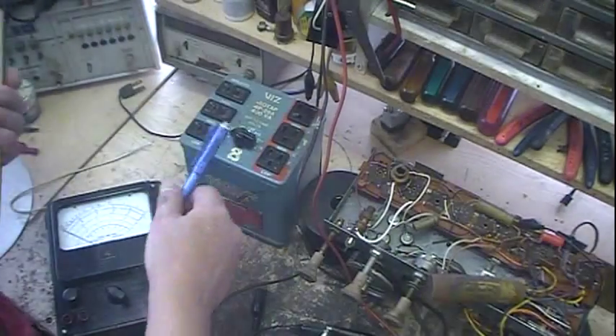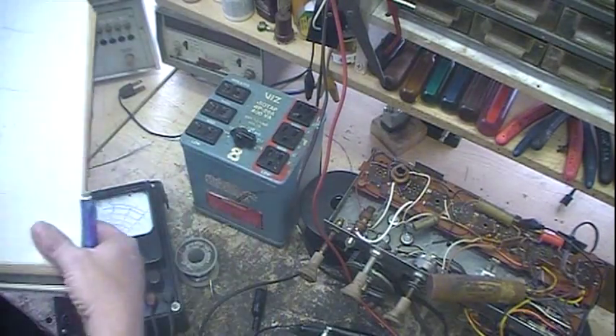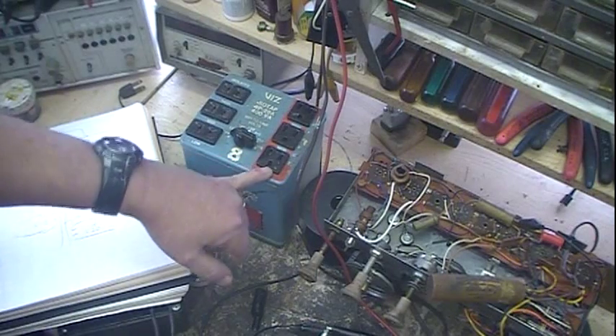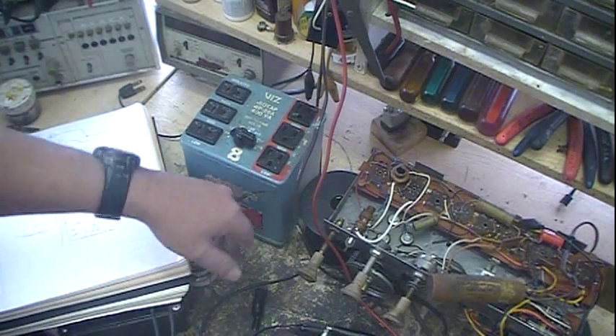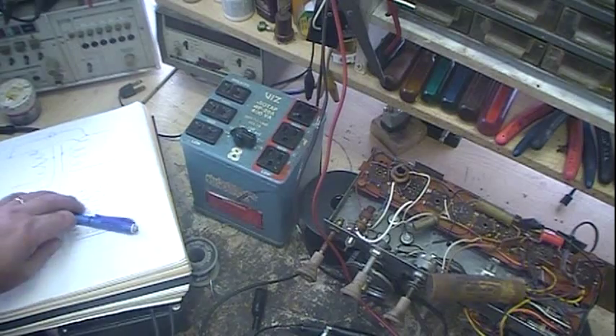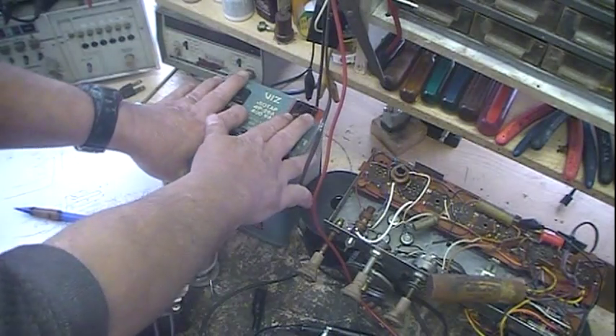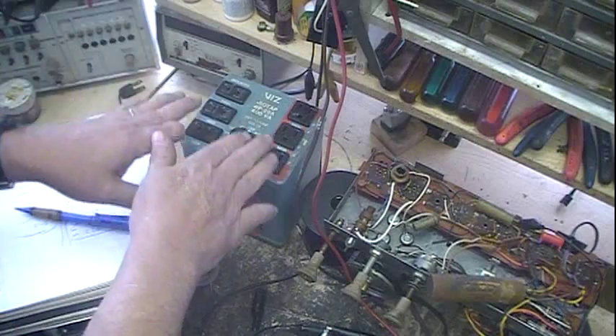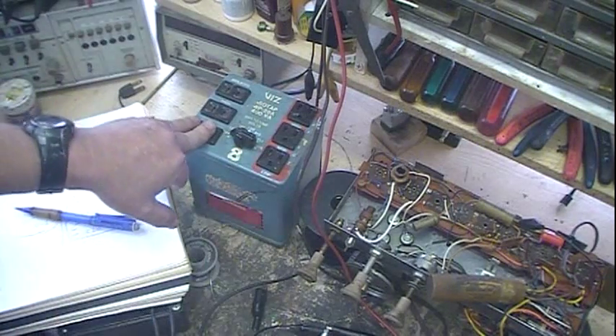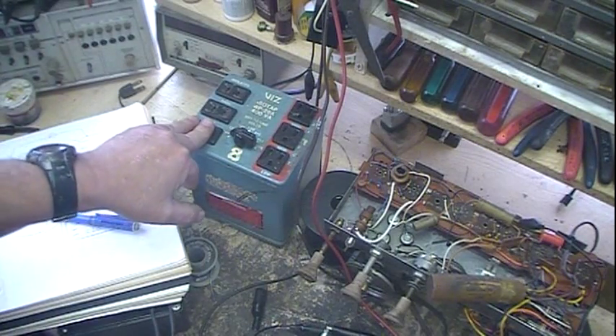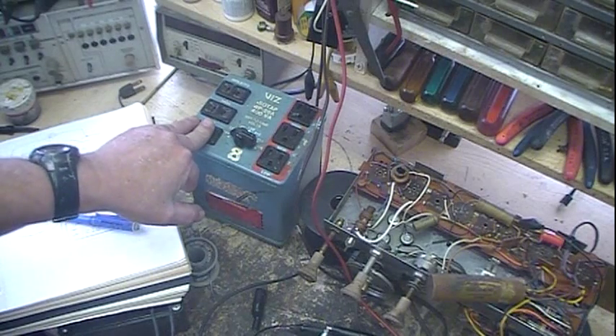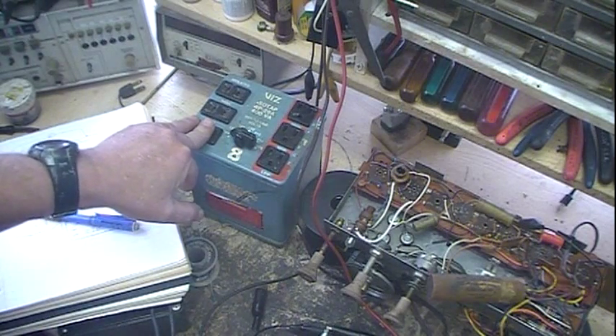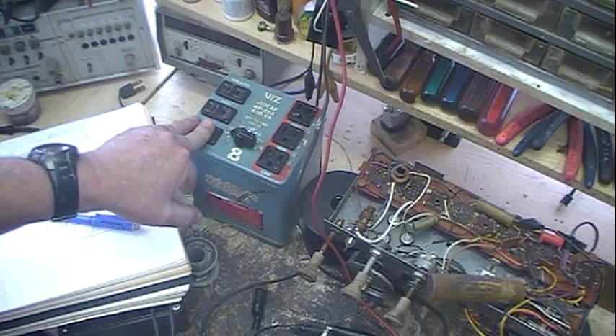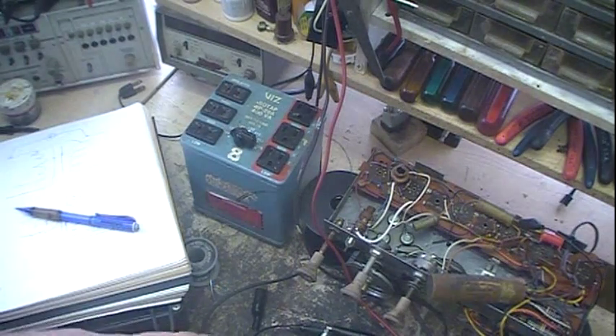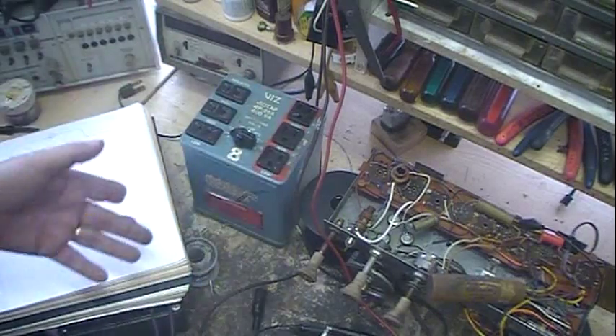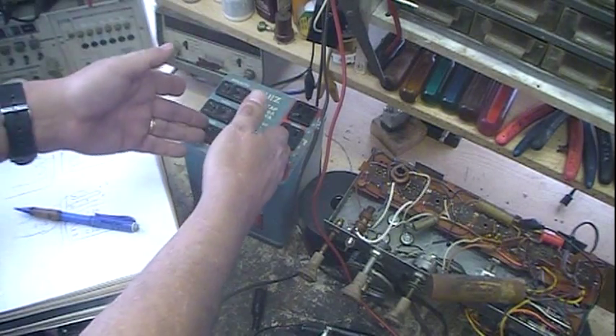Well, we did the same thing here. When I'm checking the ground on here, that's checking to the core, because that connects to the core in here. But that's the proper way, and really the only real proper true test. Now, you can use a light like I did, which will load the circuit, and if the light doesn't light, then things should be okay. But if you really want to know, take your DMM and use it.